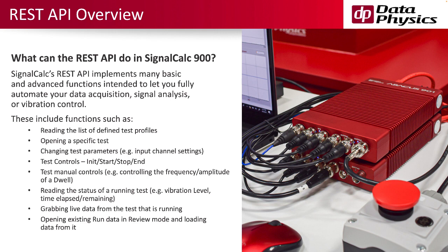You can also read and write through our digital I/O card. So if you're using the relay card to talk to, for example, a thermal chamber or another piece of lab equipment, you can access, read, and write that relay card that normally is read and written through our software. You can have full control over that through the REST interface.